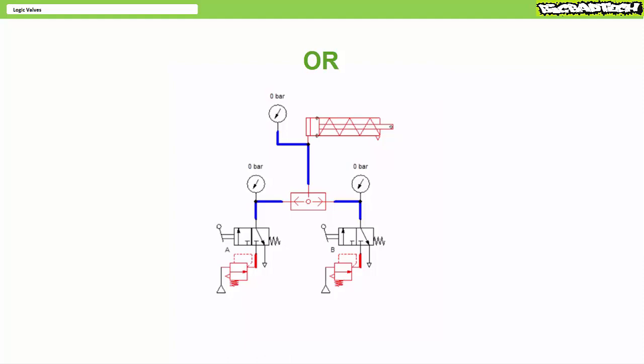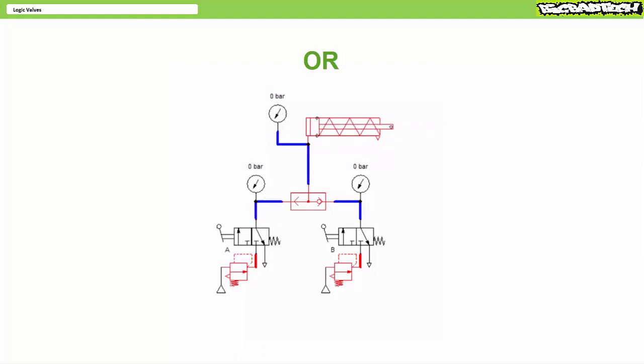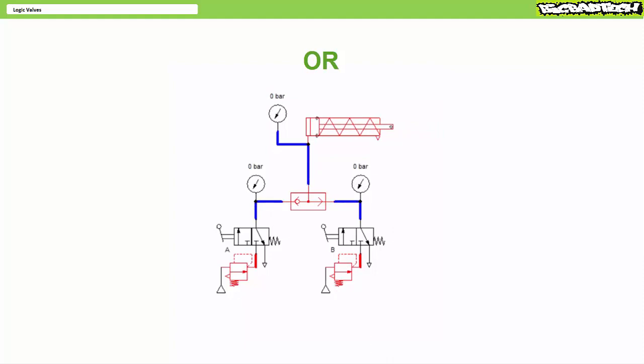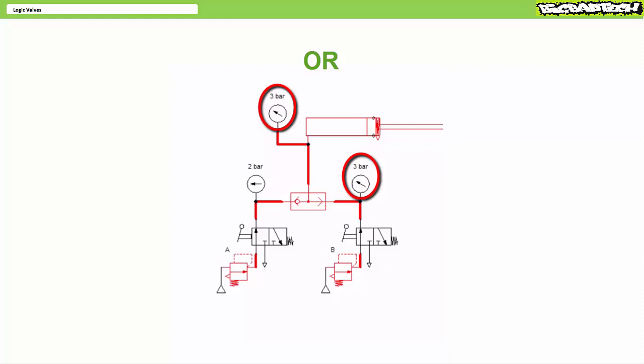When neither A nor B receive an air pilot signal, the OR valve produces no output. When only A receives an air pilot signal, the OR valve produces output. When only B receives an air pilot signal, the OR valve produces output. Finally, when both A and B receive an air pilot signal, the OR valve also produces output. You will note the OR valve selects the highest of the two pressures, notably B at 3 bar.